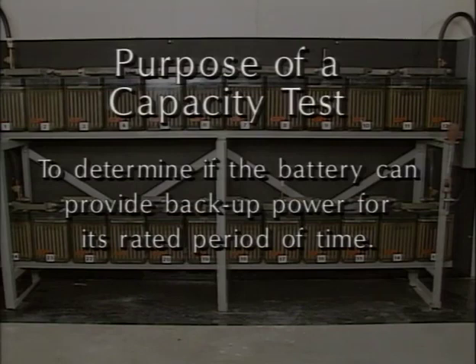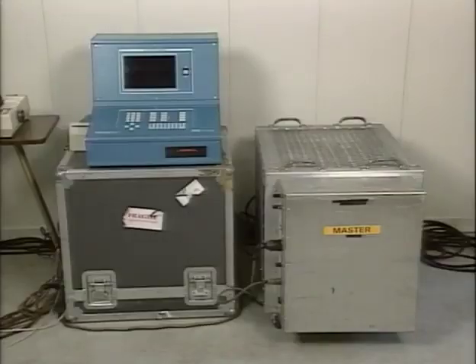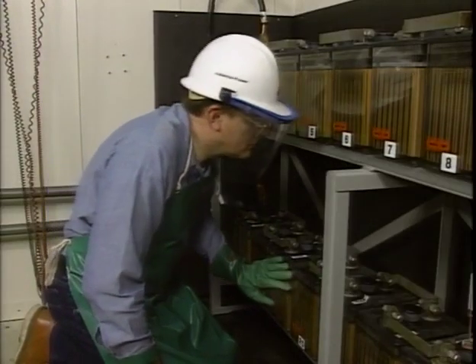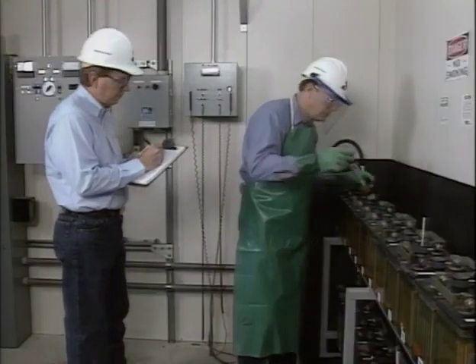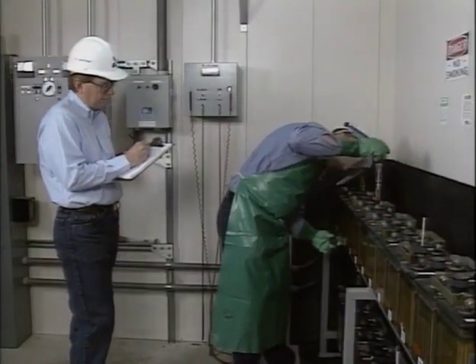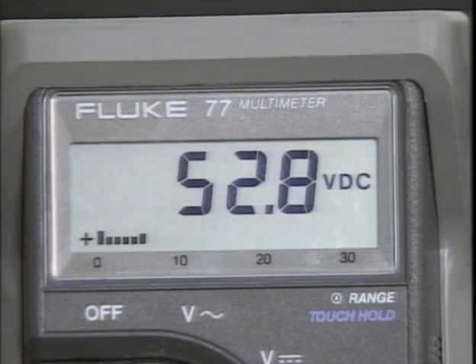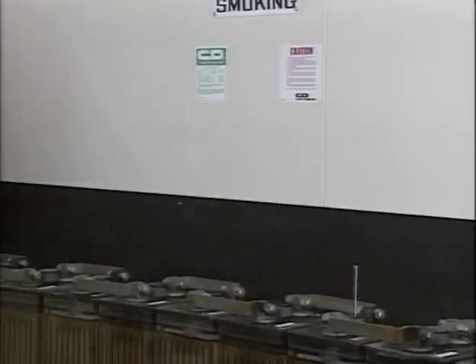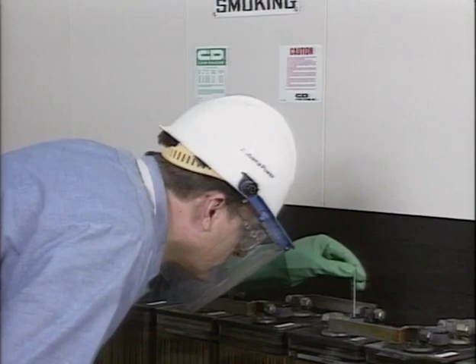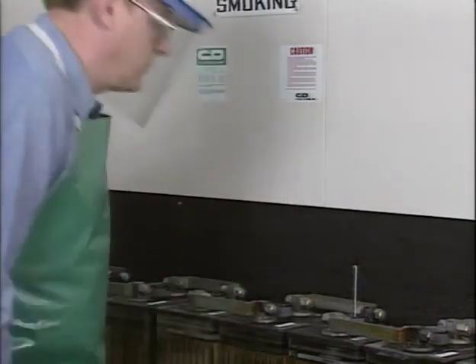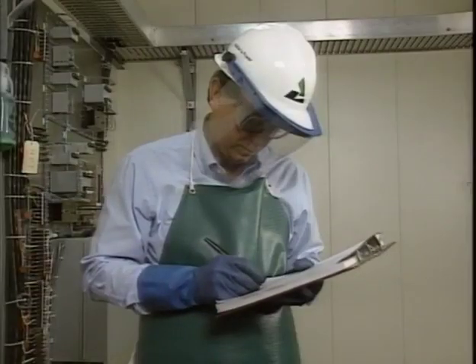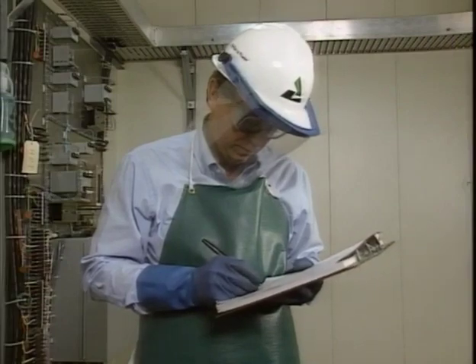The purpose of the capacity test is to determine if the battery can provide backup power for its rated period of time. Before integrity and capacity testing, several battery checks must be done, including a thorough visual inspection of each cell, specific gravity and float voltage checks of each cell, a check of the battery's terminal float voltage, checking electrolyte temperatures of selected cells, such as every sixth cell, and calculating the average cell electrolyte temperature.